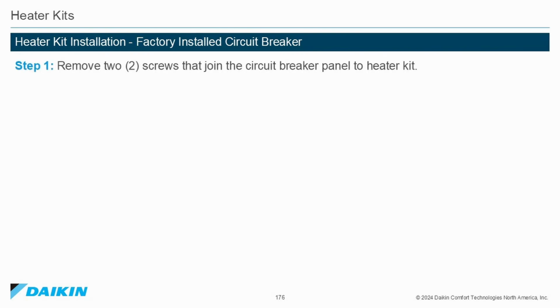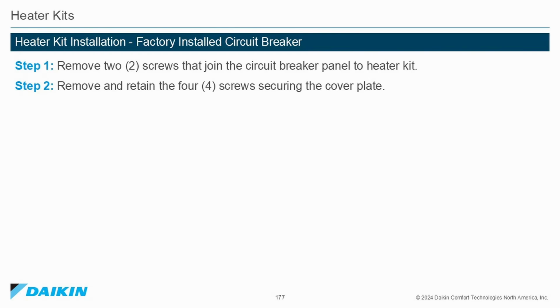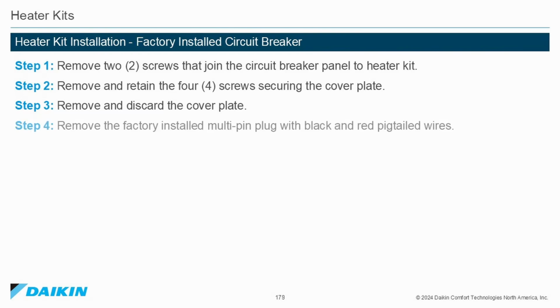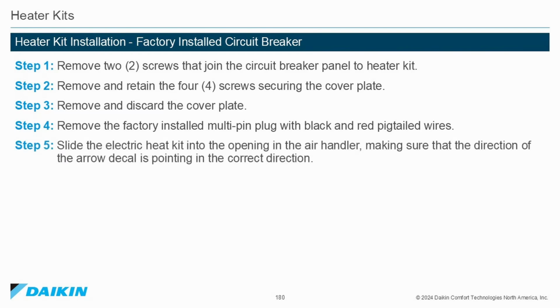Heater kit installation with factory-installed circuit breaker. Step 1. Remove 2 screws that join the circuit breaker panel to the heater kit. Step 2. Remove and retain the 4 screws securing the cover plate. Step 3. Remove and discard the cover plate. Step 4. Remove the factory-installed multi-pin plug with black and red pigtailed wires. Step 5. Slide the electrical kit into the opening of the air handler, making sure that the direction of the arrow decal is pointing in the correct direction.